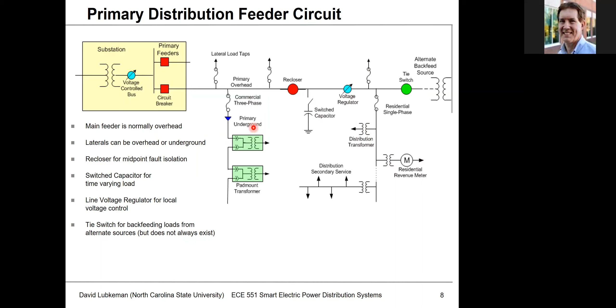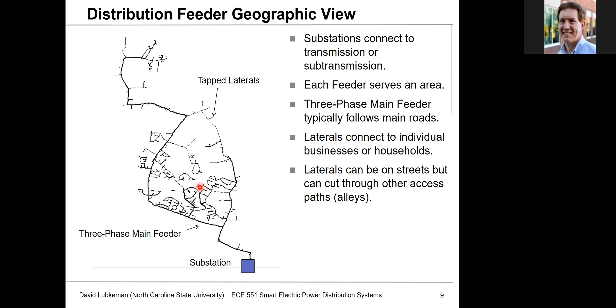As mentioned in the online class, you also have a geographic view, because these distribution circuits typically follow streets, usually main streets. When you get closer to the loads, this could follow the street, or go through alleys, but mostly they follow the streets. This is usually overhead coming out of the substation, and closer to residential areas you might see more underground cabling being used.